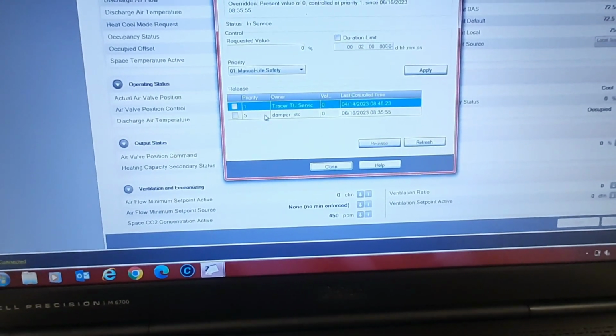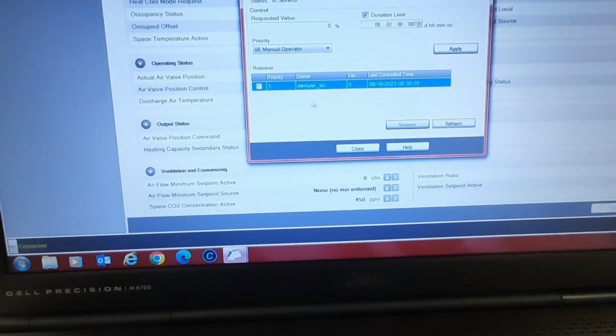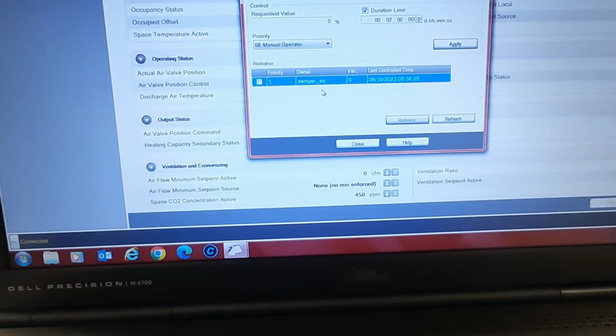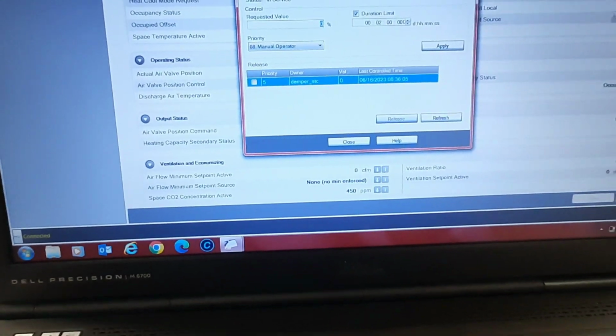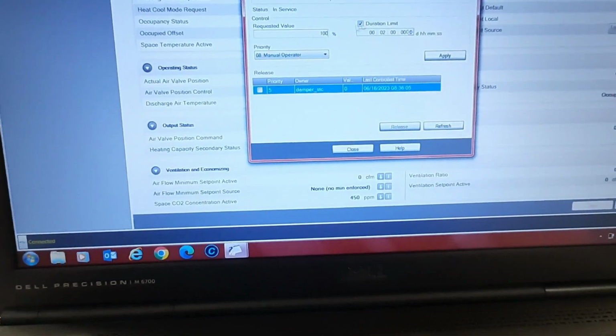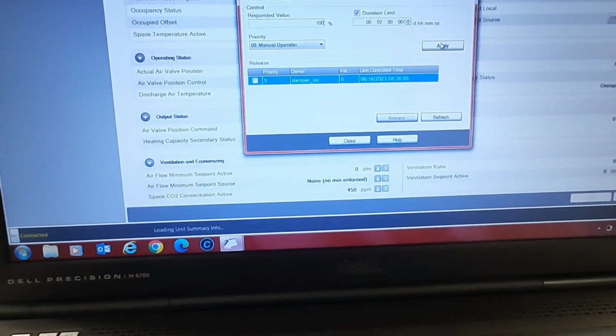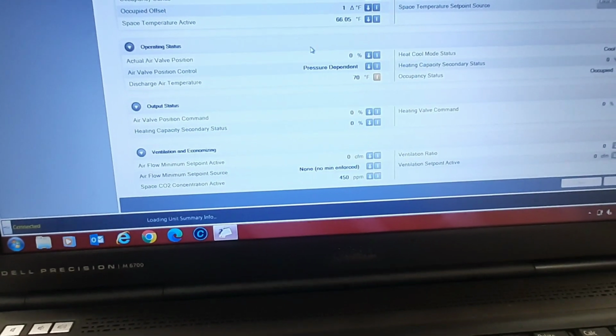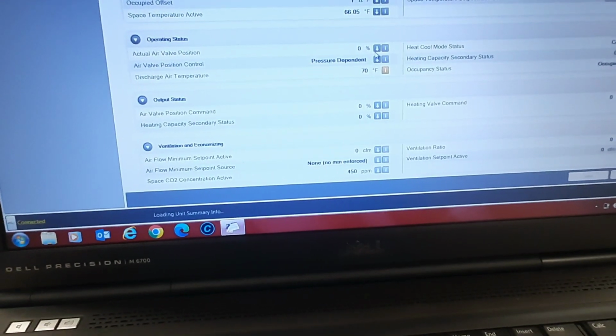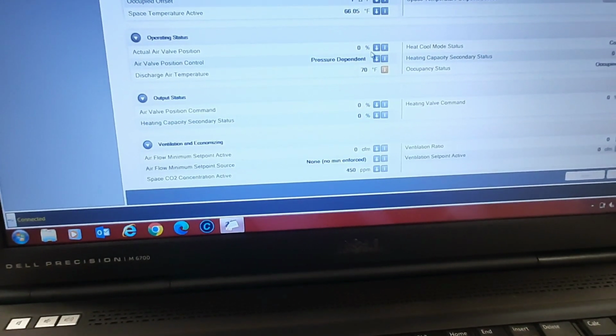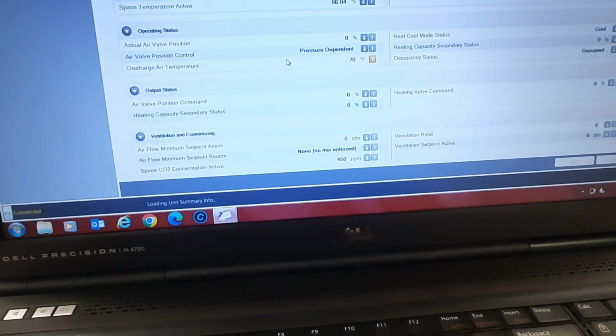Yeah, so what I'm gonna do is we're just going to release all of these overrides. The damper STC is going to be the algorithm that it's actually operating at. So what I'm going to do first is probably just set this thing to 100% and apply. We'll let it open. We should see this air valve position change. And I'm going to drive it open 100% and see what kind of CFM we get out of it. Maybe.